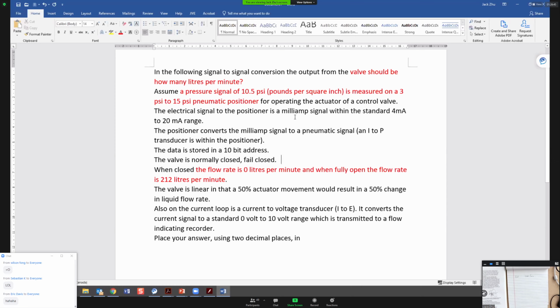So, it said use this pressure of 3 to 15 psi to operate the control valve. And the valve is normally closed, fail close. So normally closed will be 3 psi. When you fully open, it will be 15 psi. It's related to 212 liters. And they tell you it's linear. And the linear here, you think it's important, you think it's not important. Let me tell you, all the questions you're going to do, it's going to be linear. If not linear, we're not going to ask you to do it. That makes sense?